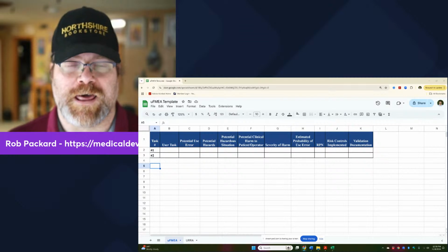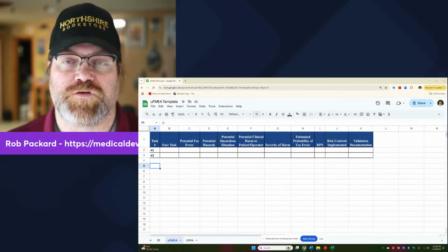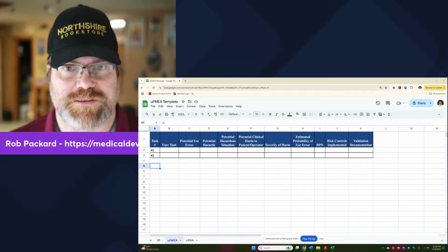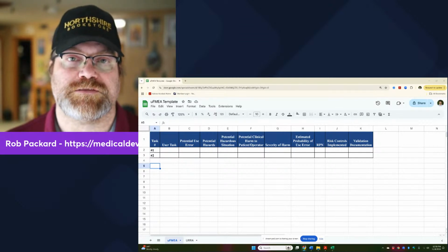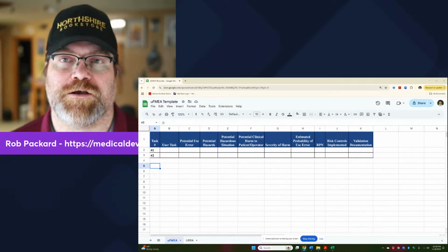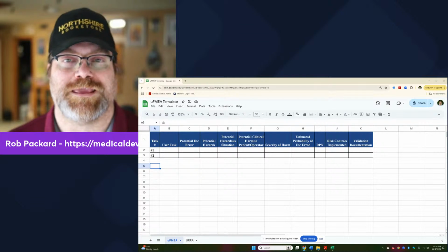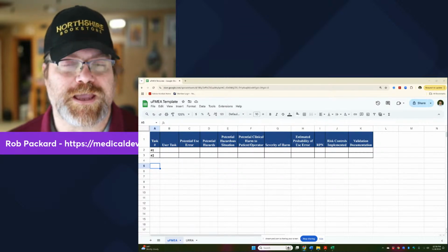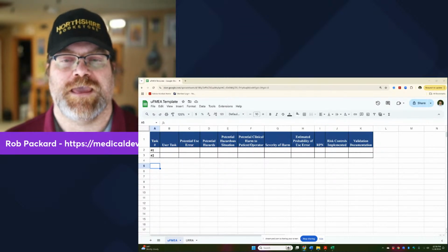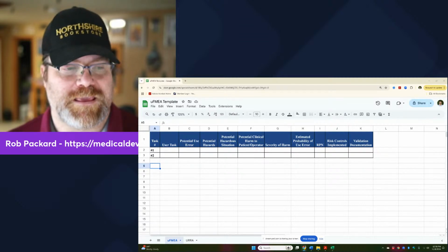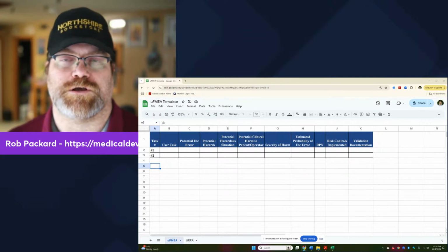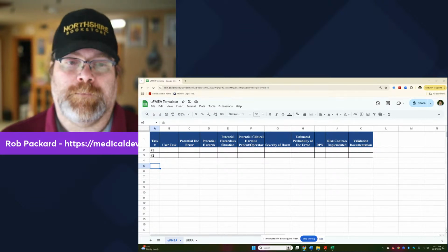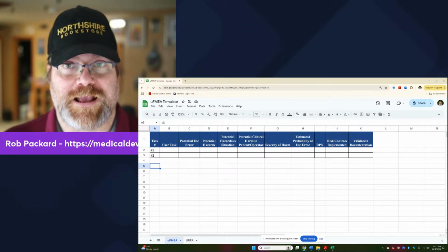Now, a lot of people will say, well, we put instructions, we put warnings on it, so we don't need to do anything else. That's not how the FDA looks at it. They want you to implement risk controls to prevent those hazardous situations from occurring without relying on the instructions. They ideally want an intuitive device, where you look at it and you know exactly how to work that device. It makes sense, and there's some measure of protection from you doing things that are accidentally going to cause harm. But we have to actually validate that it actually works that way.